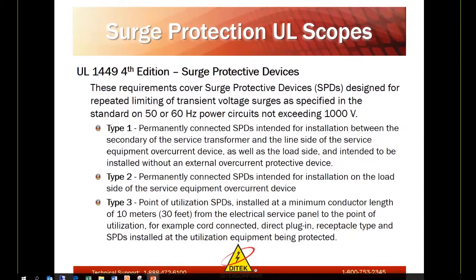Type 3 is point of utilization or point of use, installed at a minimum conductor length of 10 meters or 30 feet from the electrical service panel to the point of utilization. For example, a cord-connected device, direct plug-in, receptacle type, and SPDs installed at the utilization equipment being protected.